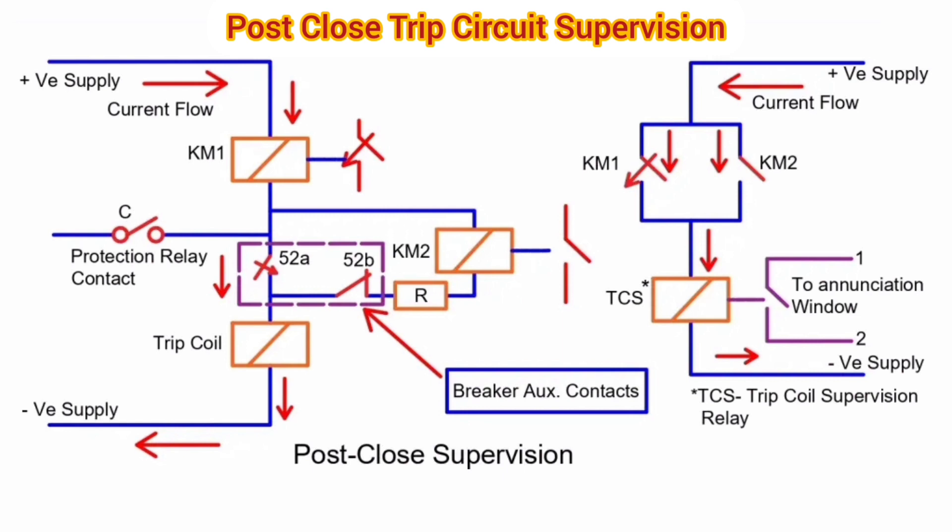In case of a fault in the supply system, KM1, trip coil, or wiring, the contact of KM1 will remain in an open state and thus the TCS will be inoperative. The NC contact of TCS outputs to the annunciation window, which shows that the breaker's trip circuit is faulty.